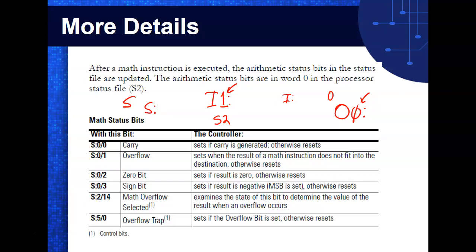So that timing register I showed you, the actual free running clock, is actually at S2:14, but all we have to do is say S:14, because it's in the status register. So those 3 registers, you don't have to specify the file number on this PLC.